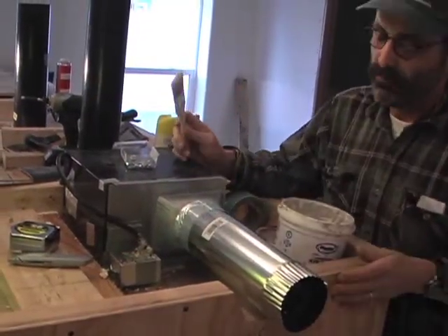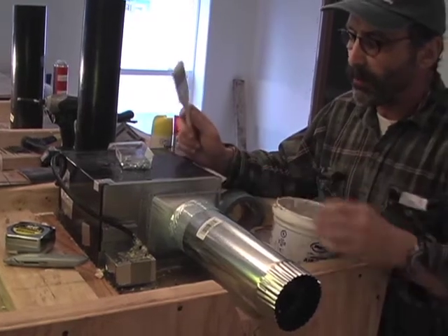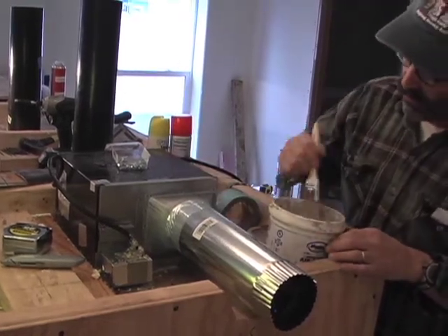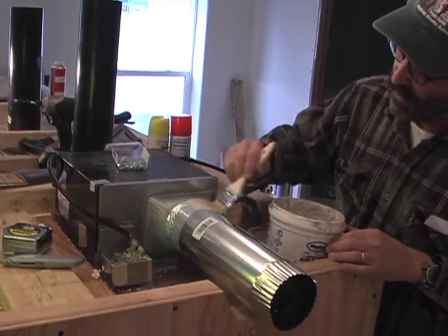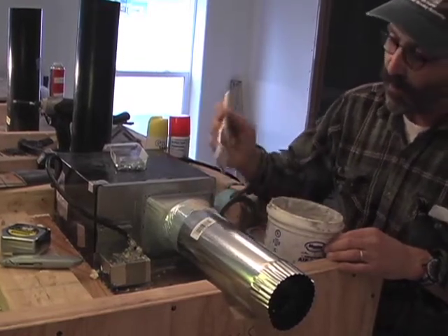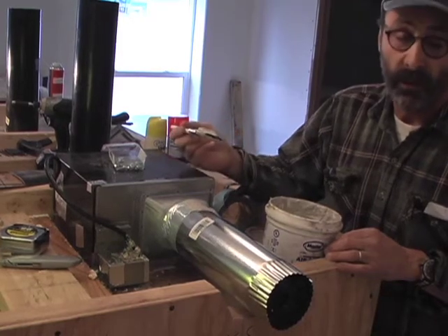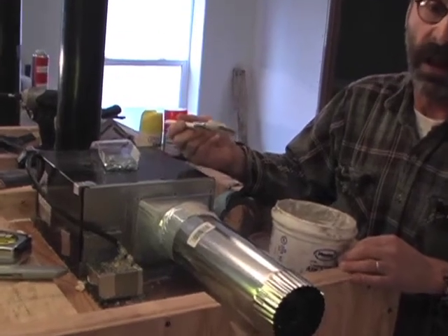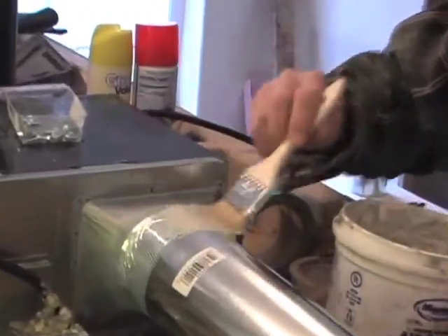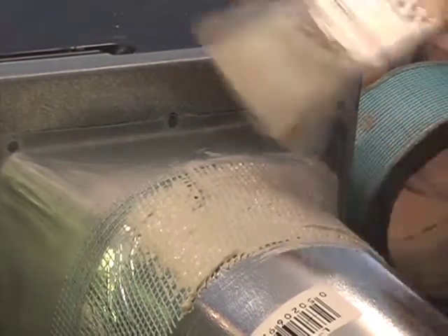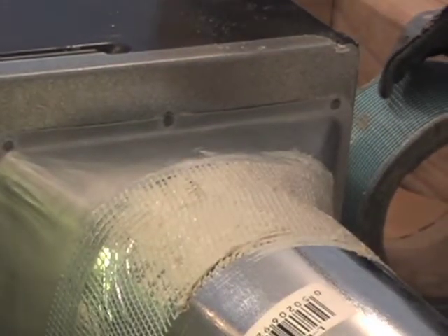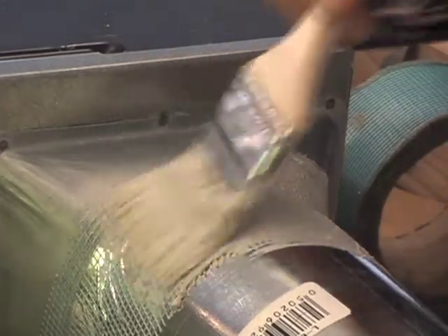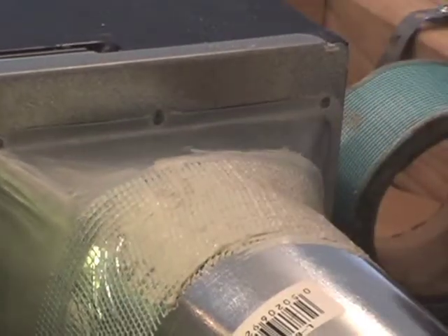There are two choices for putting the mastic on. The neatest way is with a paintbrush, where you can control it and make it look better. When you put the mastic on, too thin won't be adequate, and too much will take too long to dry and really not cure. So it's about finding that balance of filling up your mesh, without putting on so much that it won't perform. This is almost like putting a cast on a broken arm or leg. This will form a really durable seal.